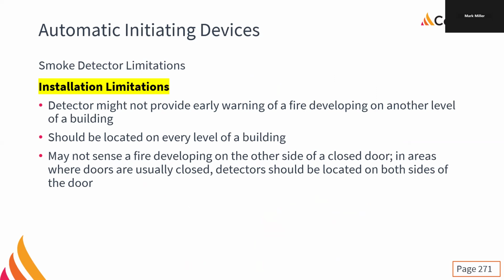Other limitations we have to worry about is, well, they can only cover so much area. A smoke detector is probably not going to provide early warning of a fire developing on another level of a building, right? That's reasonable. Like there's floors and ceilings in the way. Yeah, the smoke's not going to get there. So put them on every level of the building. Well, we just looked at the installation requirements. That's totally covered. The other thing is, if the doors are closed, well, smoke can't get through a door. It can get under the door and around the door, but not. If you have the doors closed, then you're going to have breaks in the ability to sense. So detectors located on both sides of doors that are kept closed, you kind of need to do that. But again, following the building code requirements where the smokes need to be installed, that generally covers it.